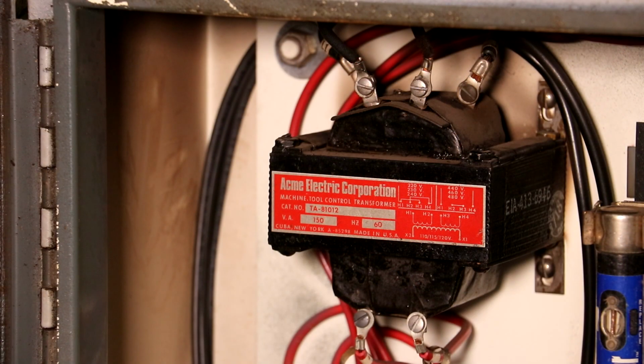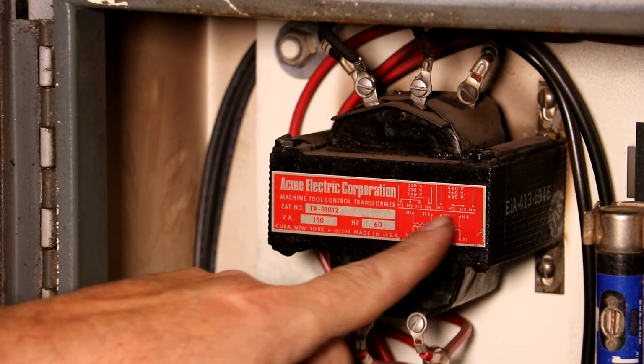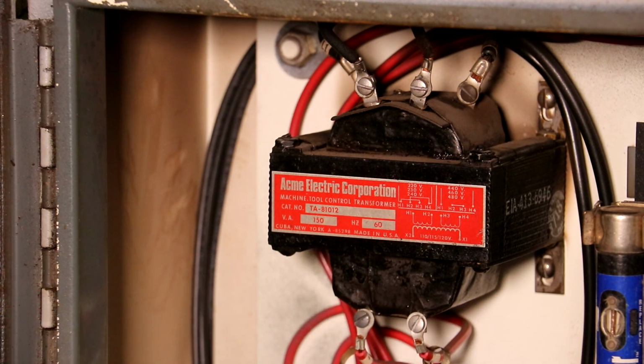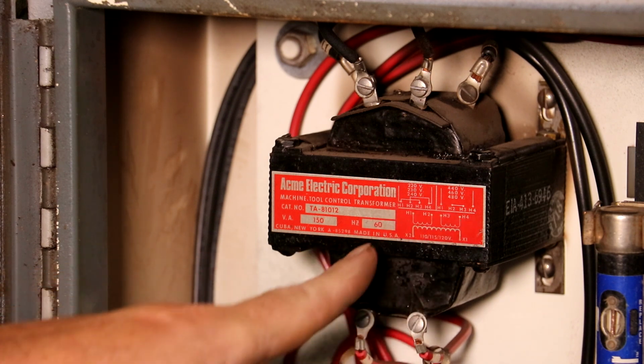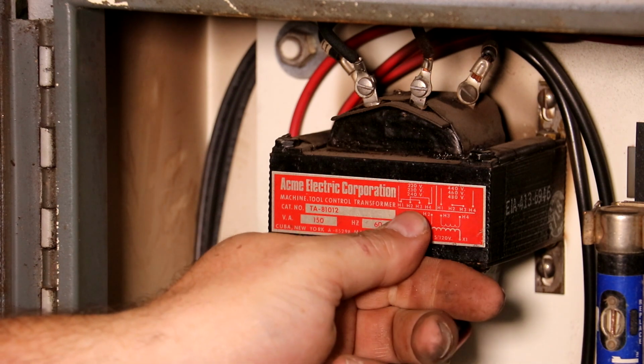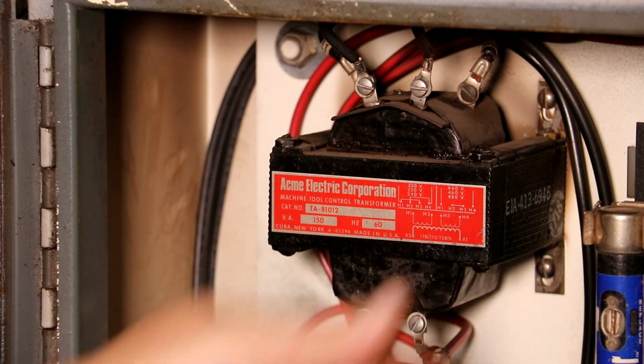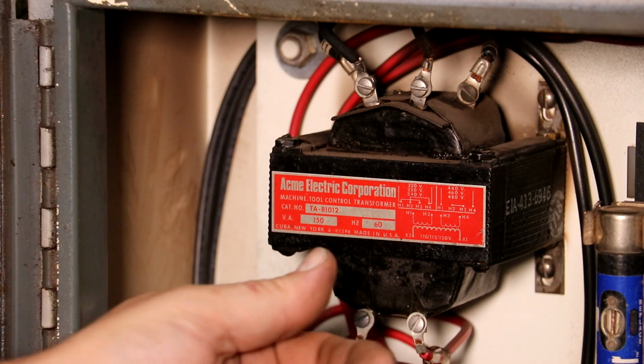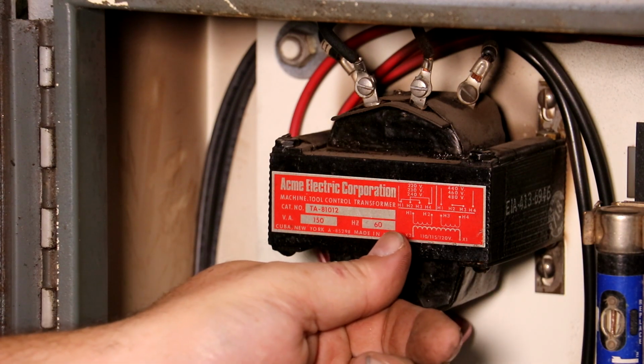All right, I got you zoomed in here, hopefully you can see this. This is the transformer, and right on the front there's a little wiring diagram. It shows basically 2 options, a low voltage and a high voltage - a wiring diagram for 220 volts and one for 440. Or it could be 240 and 480, depending on your voltage.